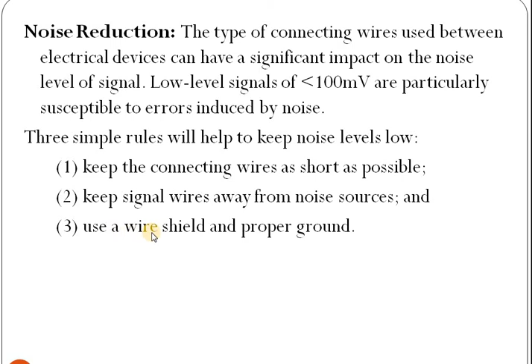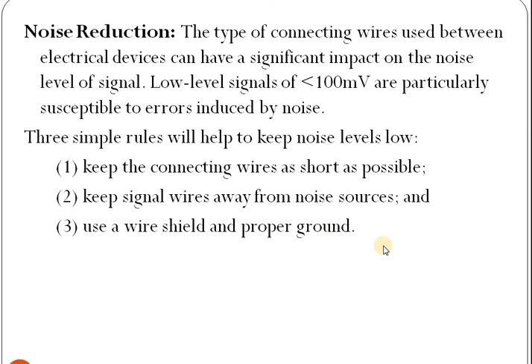When we use proper ground, any noise is moved to the earth through this ground. As a result, there is no impact of interference or noise on the particular measurements. So the first rule is to keep the connecting wires as short as possible, the second is to keep signal wires away from noise sources, and the third is to use a wire shield and proper ground. By using these three simple rules, noise is reduced. These are the techniques used for noise reduction. Okay, we stop this video with this slide.